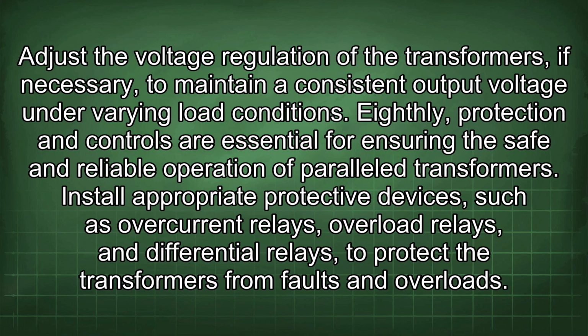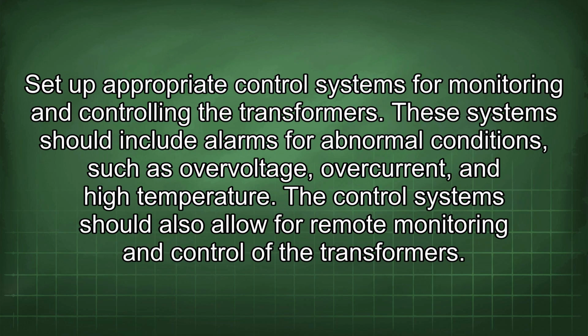Eighthly, protection and controls are essential for ensuring the safe and reliable operation of parallel transformers. Install appropriate protective devices such as overcurrent relays, overload relays, and differential relays to protect the transformers from faults and overloads. Set up appropriate control systems for monitoring and controlling the transformers. These systems should include alarms for abnormal conditions such as overvoltage, overcurrent, and high temperature. The control systems should also allow for remote monitoring and control of the transformers.